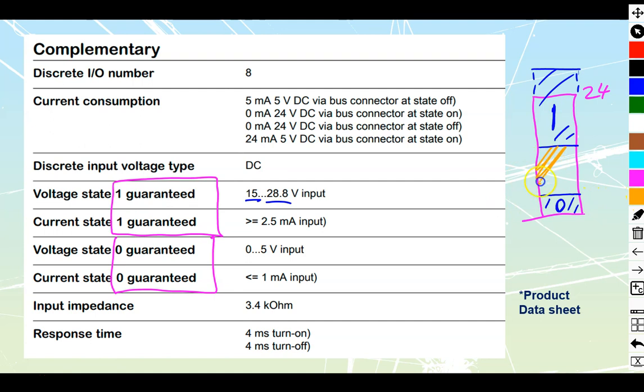It does leave us with this middle section over here. This middle section would be what we refer to as the undefined range. Undefined does not mean it does nothing. It just means that there is no guarantee that any voltage signal that you take in at these levels - let's say it was 24 volts for this thing and that we're bringing in 12 volts - they'd say that at 12 volts, they can't guarantee whether that 12 volt is going to trigger high or whether it would trigger low. So we just keep all of our signals high enough or low enough so that they're inside of one of these two ranges. Be very careful. Obviously, this thing has been rated for 24 volts, so use proper 24 volts. If you have a bit of voltage drop on it, it's not going to be the end of the world. But if you've got too much voltage drop, you sag down into this undefined range and you can no longer trigger inputs reliably.